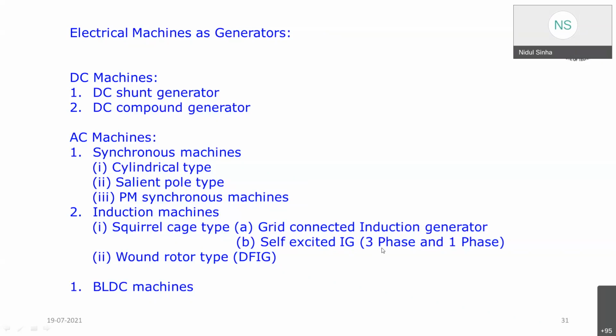The self-excited induction generator came later because of the heavy burden of reactive power on the grid from induction generators, since an induction generator cannot have its own reactive power. It needs reactive power to support its voltage build-up so it can act as a generator. So it absorbs reactive power from the grid and feeds active power to the grid.